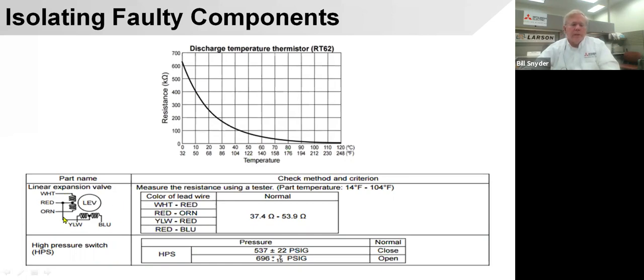The LEVs are basically, the red wire here is a common wire, so you can check between red and white, red and orange, red and yellow, and red and blue, and you should be at this sort of ohms. The difference between this and this is at 14 degrees, you're going to be at 37 ohms. At 104 degrees, you'll be at 53 or 54 ohms. So as long as you're between there, you should be fine. The LEV little motor on the top should be fine. And the high pressure switches, this is when they open. You can see here we open at about 700 pounds and close at 537 pounds.